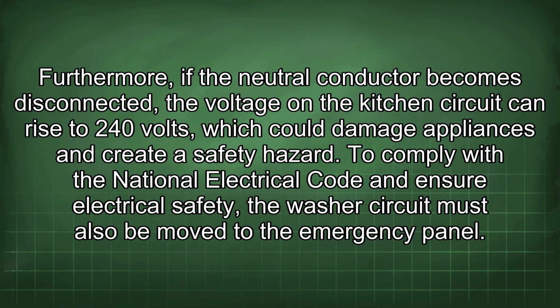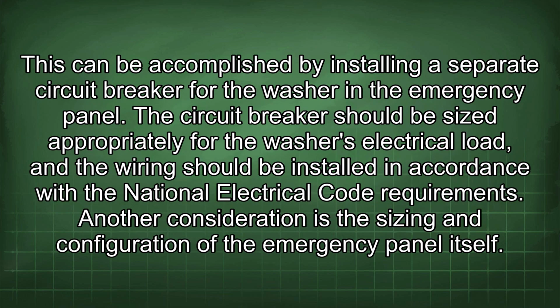To comply with the National Electrical Code and ensure electrical safety, the washer circuit must also be moved to the emergency panel. This can be accomplished by installing a separate circuit breaker for the washer in the emergency panel. The circuit breaker should be sized appropriately for the washer's electrical load, and the wiring should be installed in accordance with the National Electrical Code requirements.